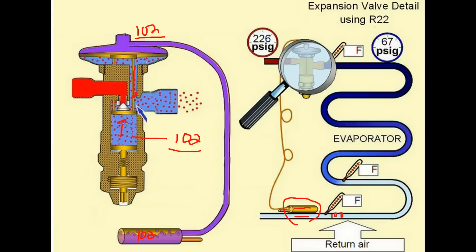So we can't maintain superheat or any other properties of a TXV. But you can see that if we just have one opening force, which is the bulb pressure, and one closing force, which is the suction line pressure, they will eventually, after running, even out so that the pressure inside of the bulb and the pressure inside of the suction line, the temperatures and pressures are the same.